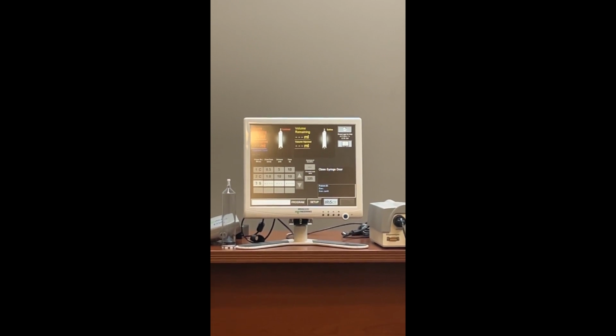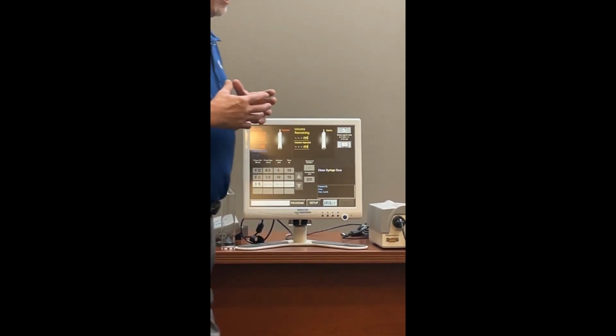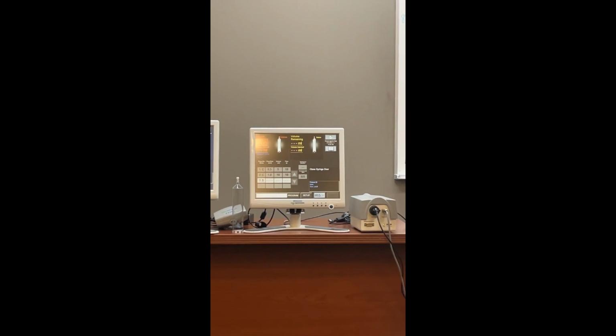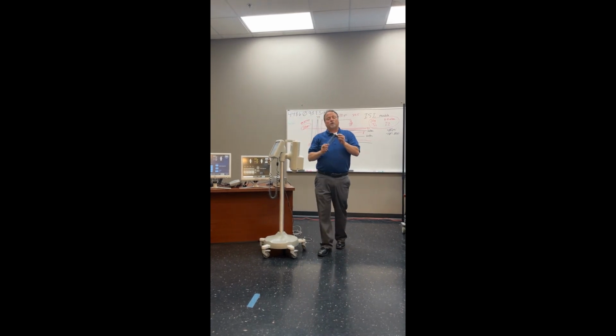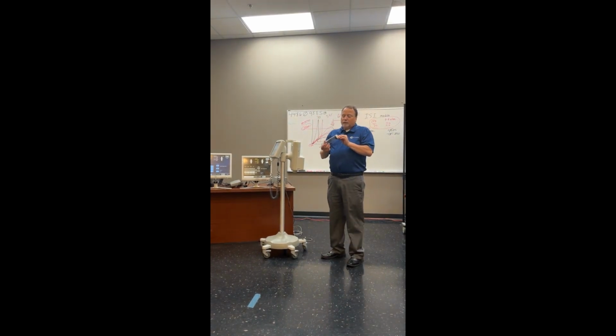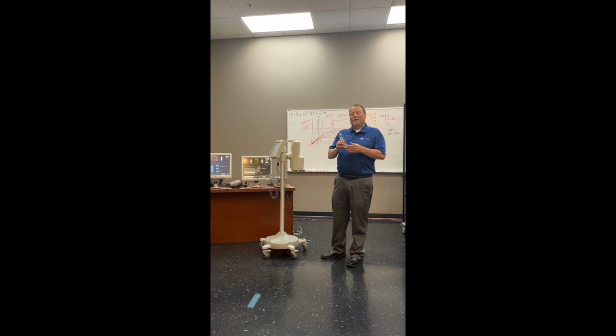It's unique that way. The actual injector head itself is very simplified inside. Syringes. If you're servicing these, they design these syringes. We all know injector syringes are one-time use for the patient. But if you're servicing them, you don't want to go through a syringe every time. So you have to think a little bit differently than Acist does.